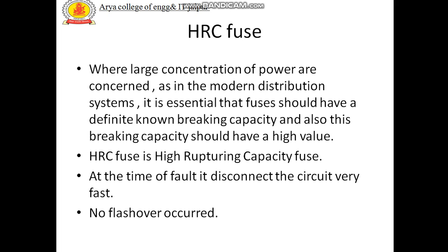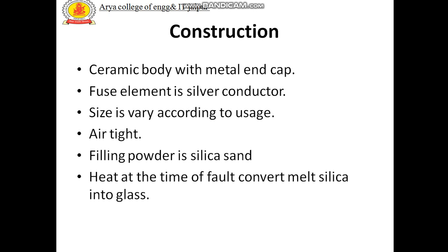In an HRC fuse, the fuse element is surrounded by an inert or quenching medium and completely enclosed in an outer body of ceramic material having good mechanical strength. The unit in which the fuse element is enclosed is called the fuse link. At the time of fault, it disconnects the circuit very fast. There is no flashover.